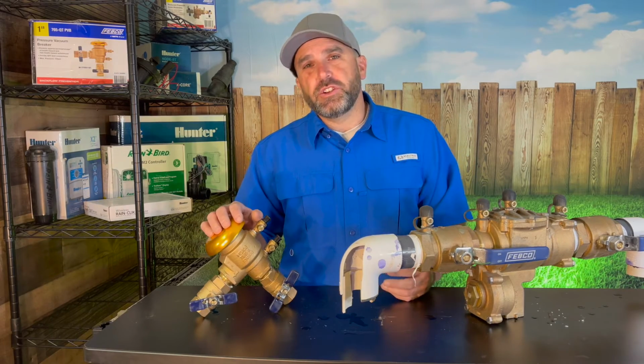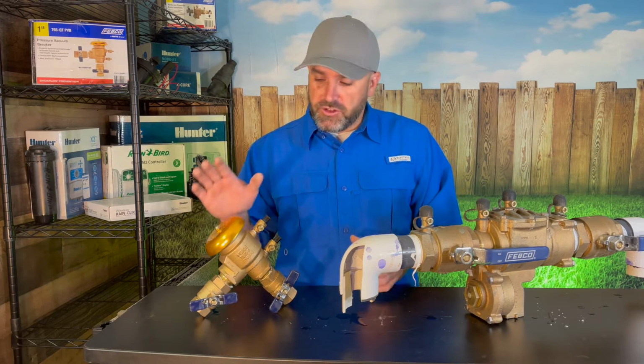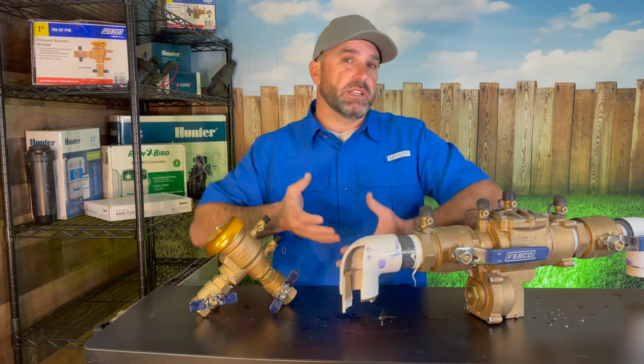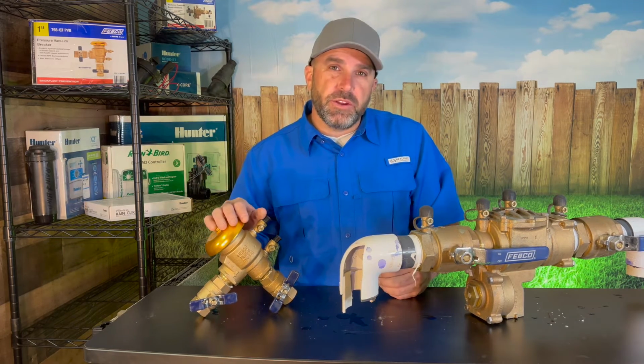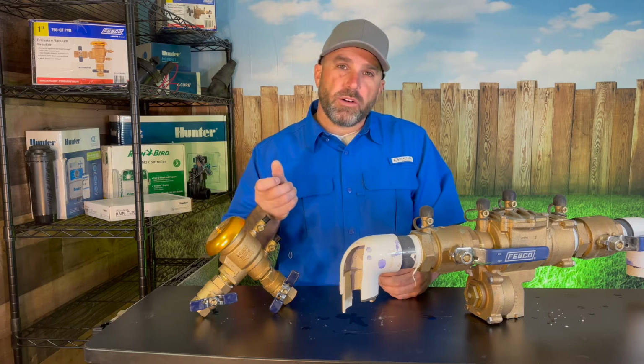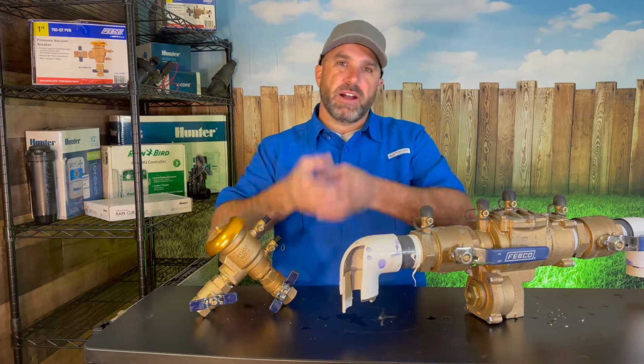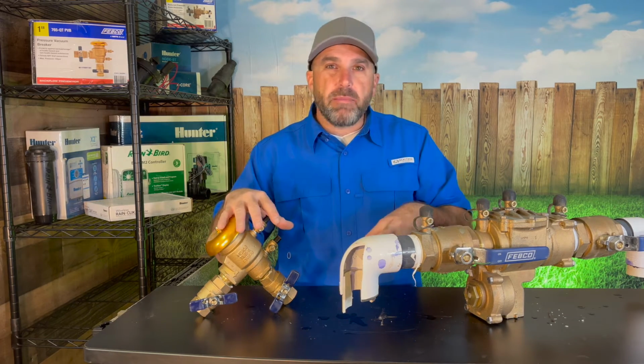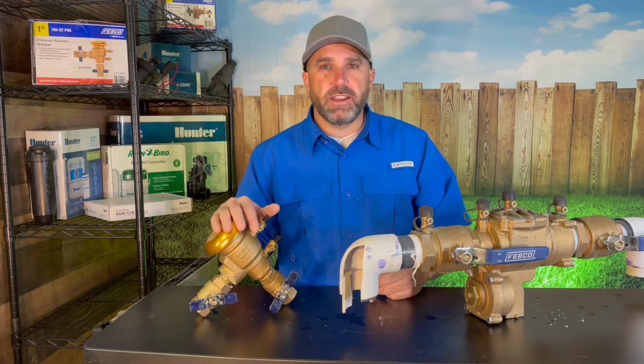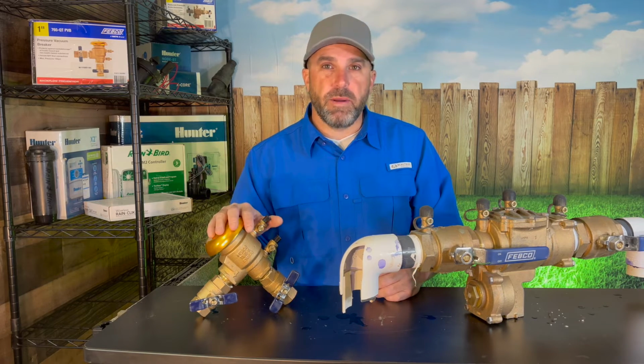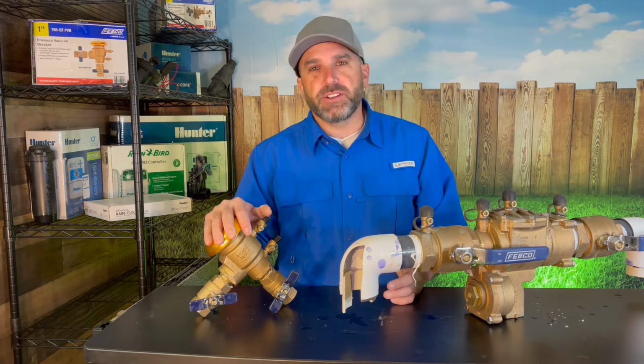There are some of these units that are installed in a way that you can just take the backflow device completely out. If these are installed with unions, sometimes you'll shut the water off and you'll take this backflow device completely out, put a cap back on or something like that so it's not leaking, and then you won't have to worry about your backflow device at least freezing and breaking.